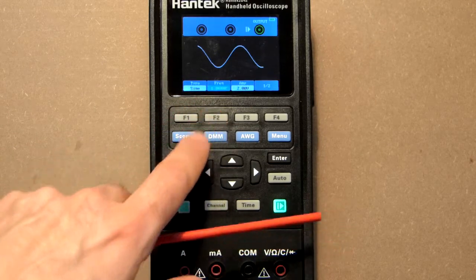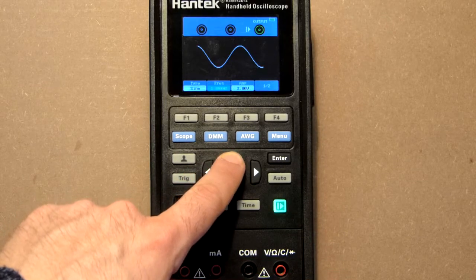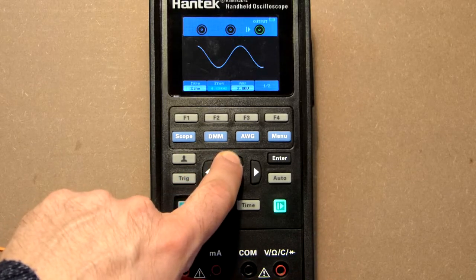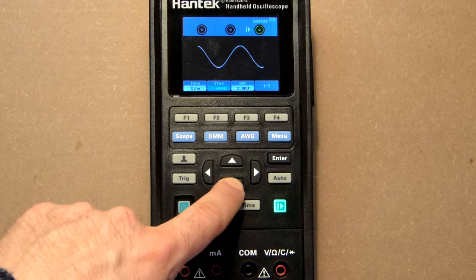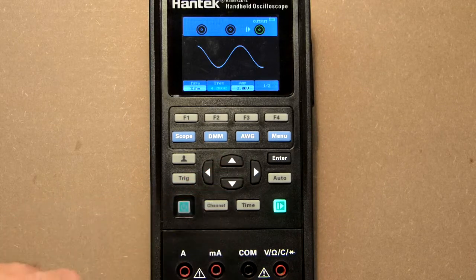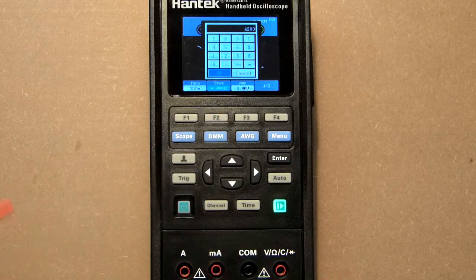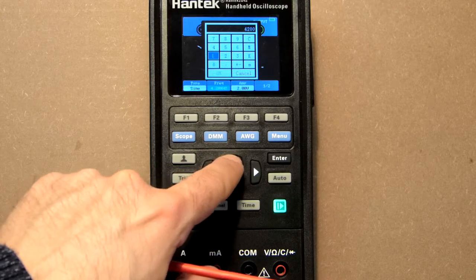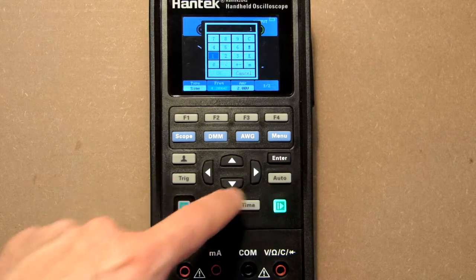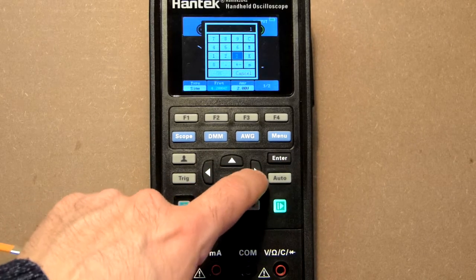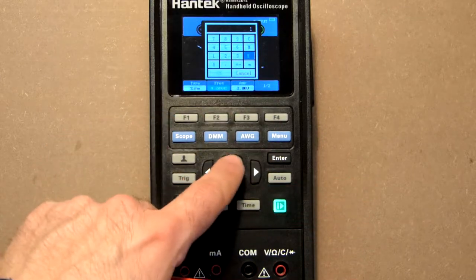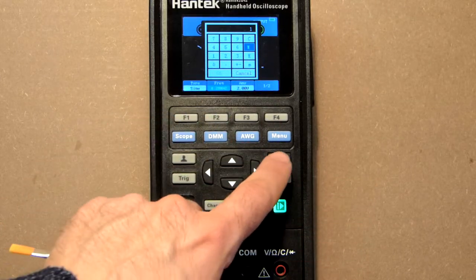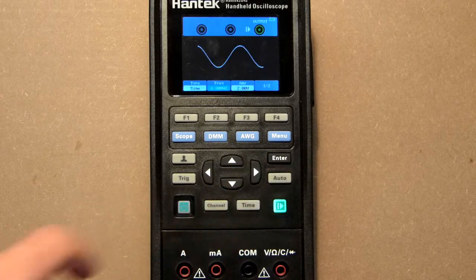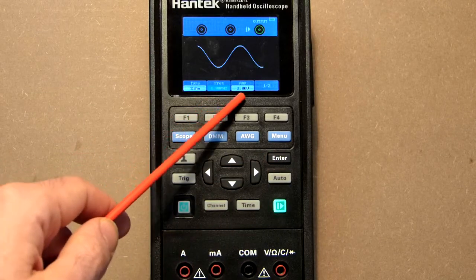Frequency can be changed with the help of these two buttons - you can increase or decrease, but if you press a second time, you get a numeric pad. For example, to generate a 1 megahertz signal, press 1, enter, then choose kilohertz or megahertz - let's say megahertz - enter, and we have a 1 megahertz signal with amplitude of 2 volts.